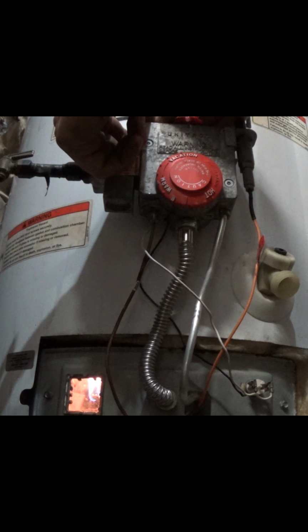That is a fix to the thermocouple rather than having to go and replace it and take it out altogether. So go ahead and continue to hold this down. Looks like I have about 20 seconds left to go. And hey, I got a flame. It's lit. That's good. Everything was cleaned off.